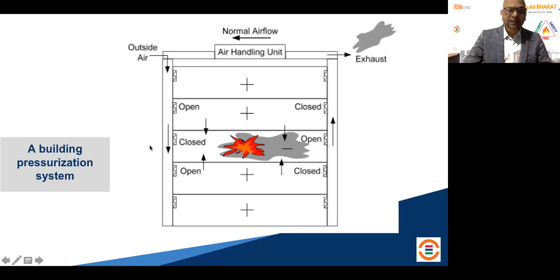That's how it is. Yeah, but the important aspect that I want to highlight here is that this is purely an engineering way. You cannot apply standard rules that, okay, I understand today smoke dampers are going to do a job, so let me install smoke dampers everywhere throughout the building. That's not the right way. As I mentioned in the previous slide, it is to be coordinated with auxiliary systems. Unless you have that integration done, it is not going to be possible to make sure that your smoke management is effective or efficient. Yeah. So let's look at the other scenarios.